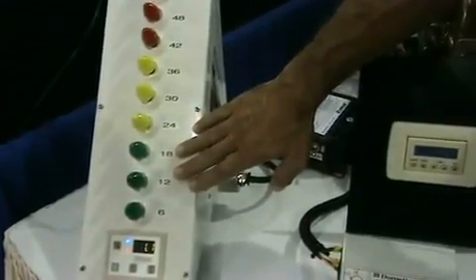When the compressor starts up without the Smart Start, it draws 49.1 amps. If we run the same test with the Smart Start engaged, you're going to see something very different.